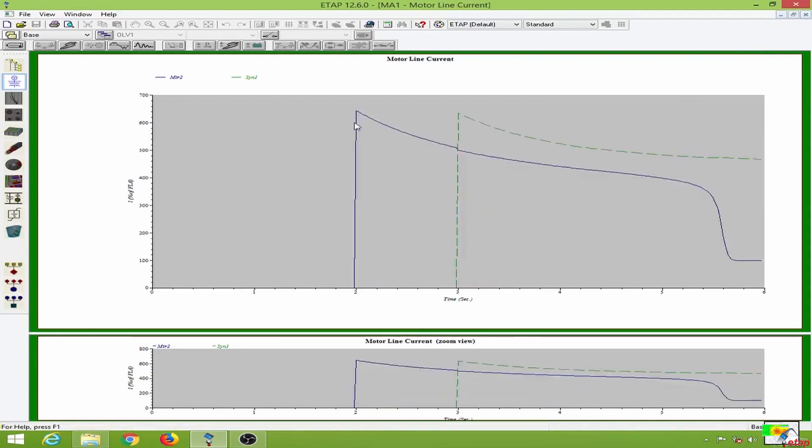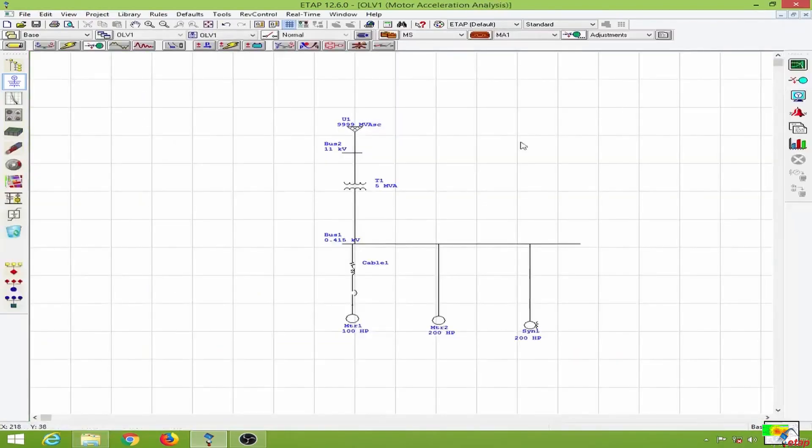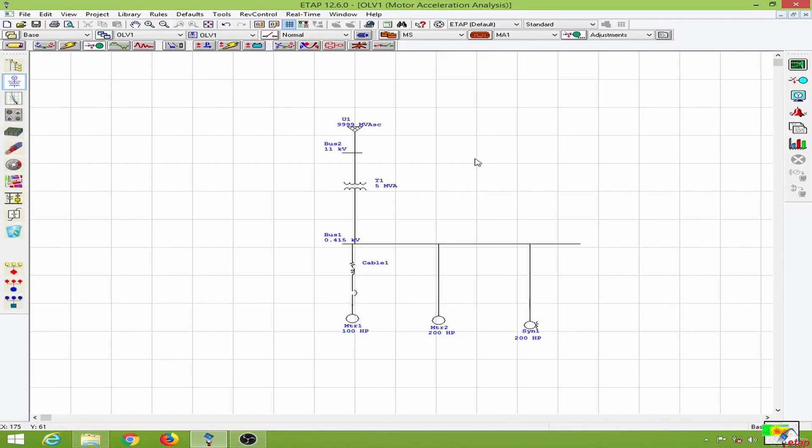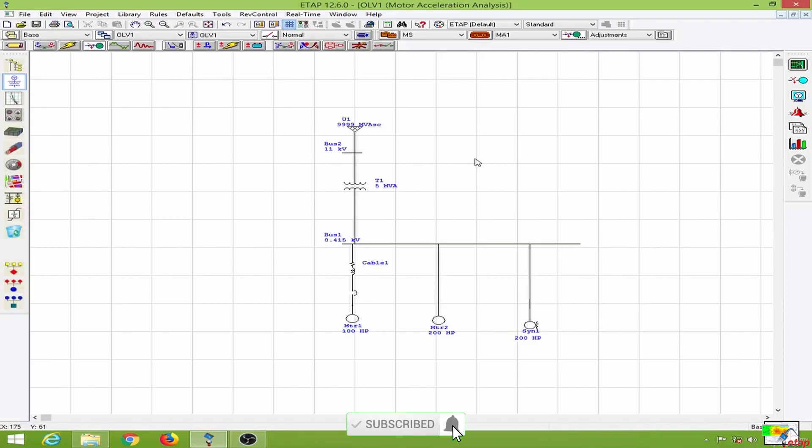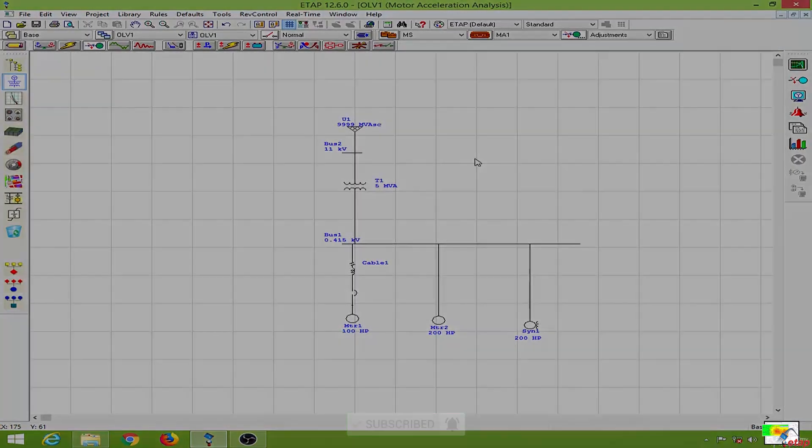And this is the motor line current, which is similar to the motor terminal current that I explained before. And this is how you conduct a dynamic motor acceleration analysis in ETAP. In the next lesson we will learn to introduce starters and variable frequency drives in order to limit the inrush current. So see you in the next lesson.